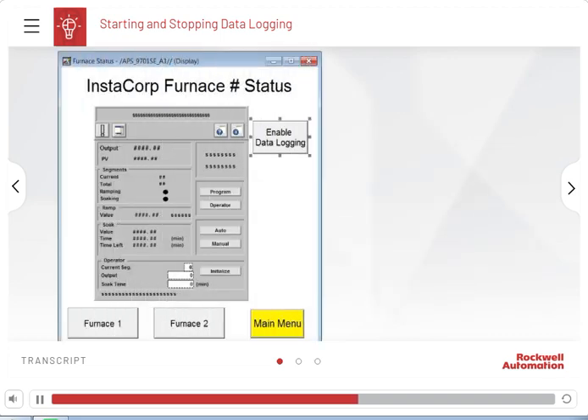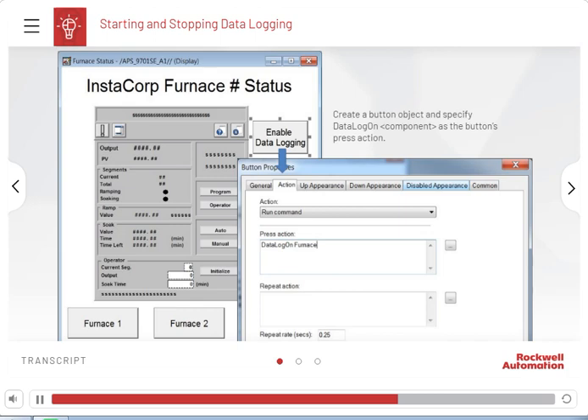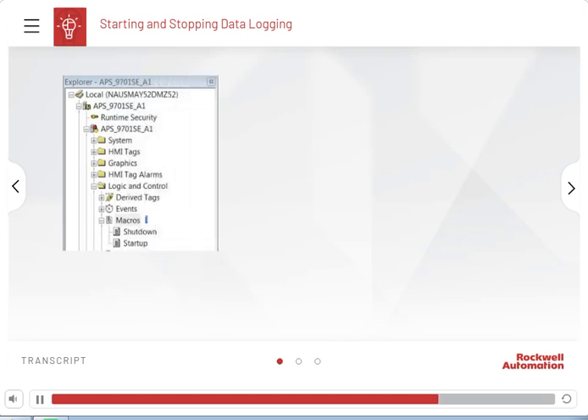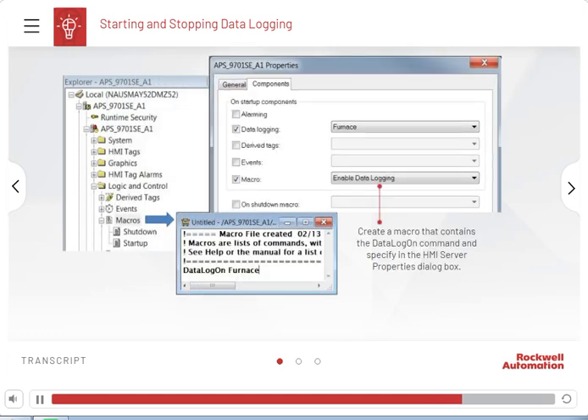Another way is in the graphic editor — create a button object and specify 'data log on component' as the button's press action. In the macros editor, you can create a macro that contains the 'data log on' command, and then in the HMI server properties dialog box, you can specify the macro. The specified data log macro will run when the HMI server runs.